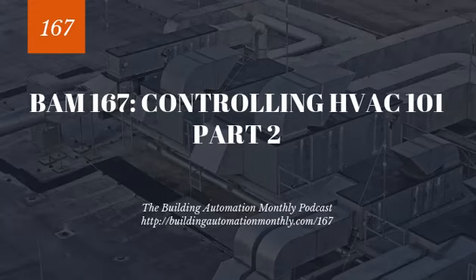And then finally, life safeties. Those are primarily fire alarm and smoke detectors. All of these typically are going to be wired as a normally closed safety for your control circuit that's running through them, and they will only break that circuit from that normally closed state when they're actually in alarm.